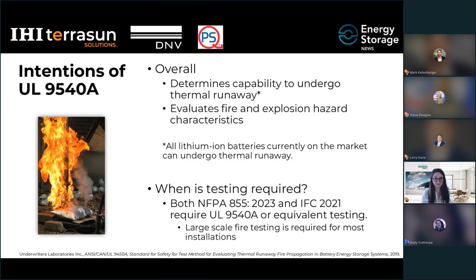It is important to understand here that all lithium-ion batteries currently on the market have the propensity to undergo thermal runaway, which is why testing is so important. So when is testing required? Both NFPA 855, the 2023 version, and the 2021 version of the International Fire Code, the IFC, require UL9540A testing or equivalent testing. And then the large-scale fire testing, again, is required for most installations. It's important to note here that the UL9540A test is not a pass-fail test. Instead, there are 4 outlined levels of testing, each with their own performance criteria. In order for a technology to end testing at a certain level, the performance criteria do need to be met. The performance criteria are designed to answer some of these questions outlined here.